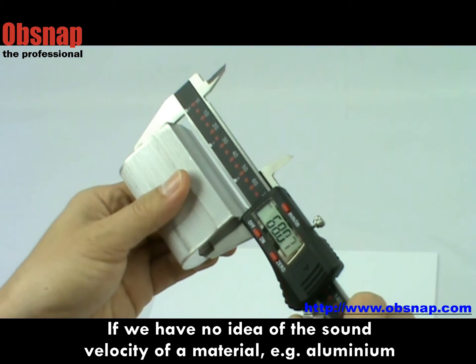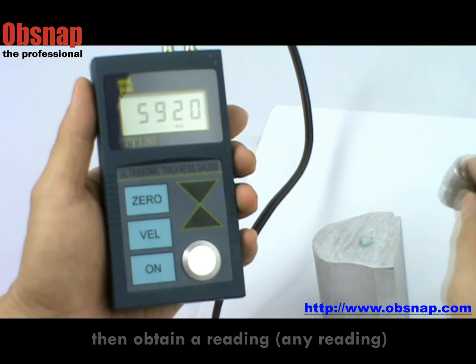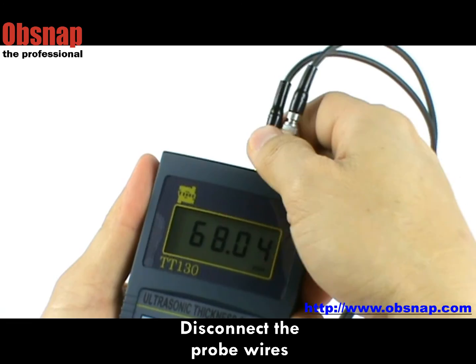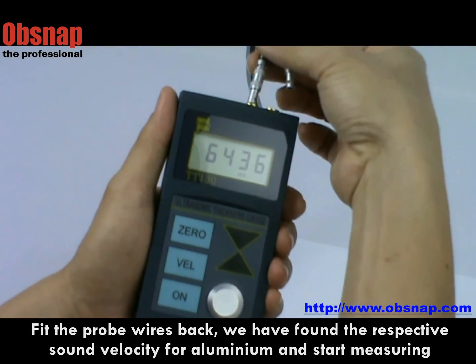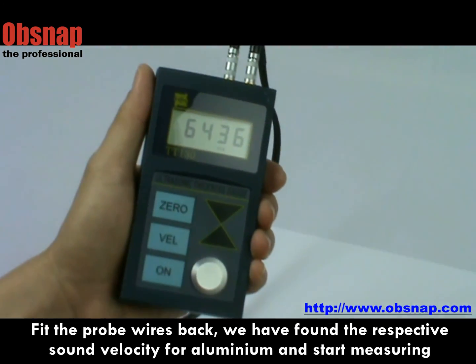If you have no idea of the sound velocity for the material — for example, aluminum — we first measure the thickness of the material: 68.04. Then obtain a reading, any reading. We disconnect the probe wires and adjust the reading to 68.04, followed by pressing the VEL key. Fit the probe wires back, and we have found the respective sound velocity for aluminum and can start measuring.